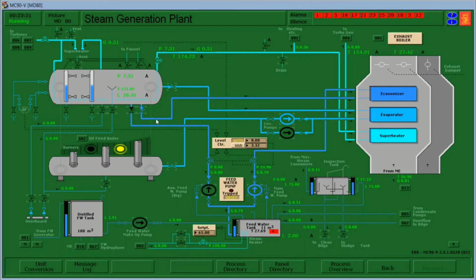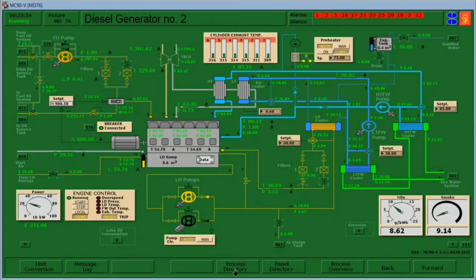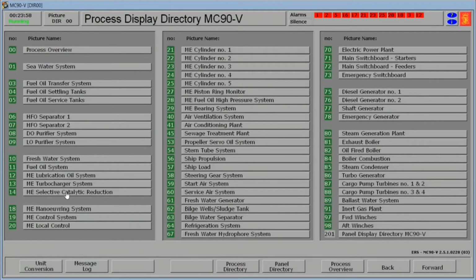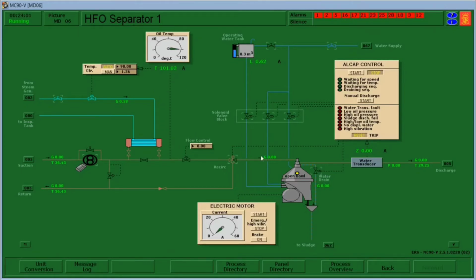Proceed, we check the boiler. Okay. For the separator, start the electric motor. Same for the purifier 2. So open, set the flow control to 10. Suction. Same for the separator 2. So waiting for speed. So we will wait till the current reaches 10.